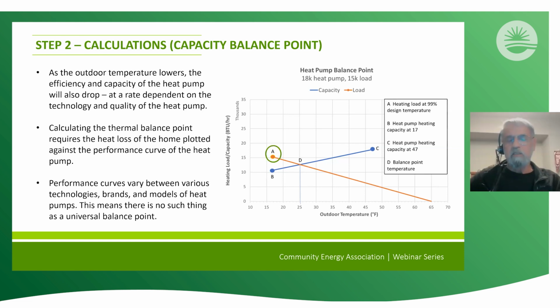Yeah, Ryan, can I add? Yeah, go. That line C to B, that's the heat pump capacity, and it tends to correlate to its efficiency as well. Its capacity will drop off, its efficiency will drop off. That C is at about 47 degrees Fahrenheit. That is the nominal capacity. All heat pumps are at basically the same line at the starting gate, 47. That's their nominal capacity. So something that says it's a 3-ton is at 47.